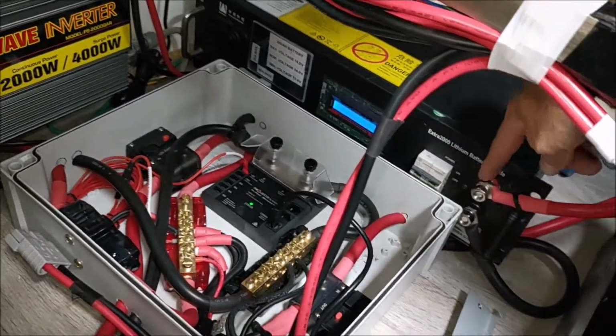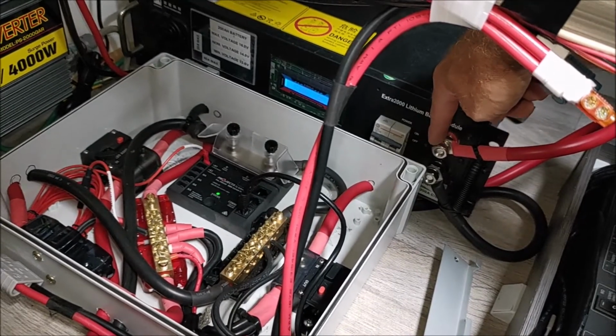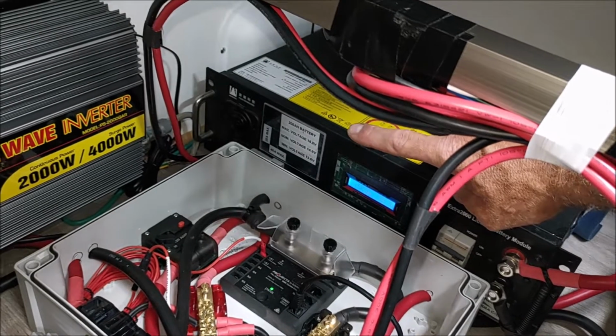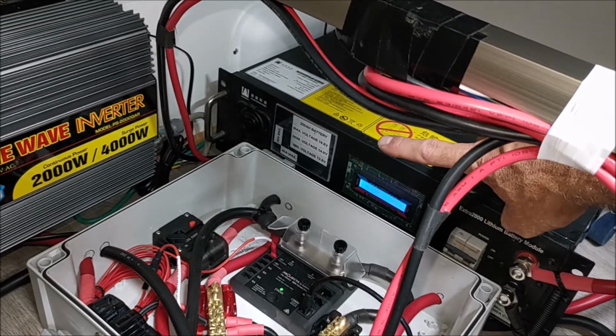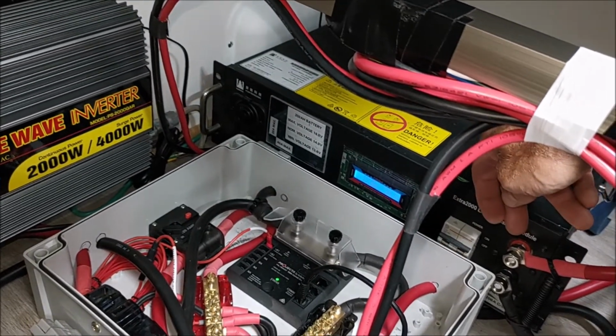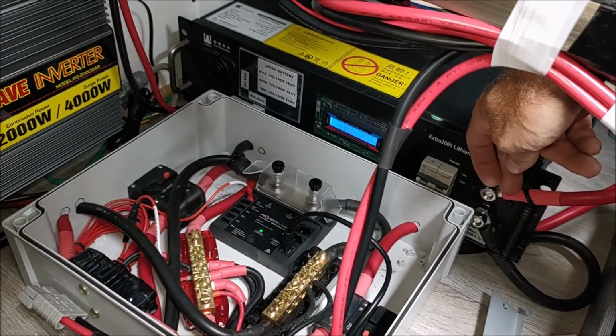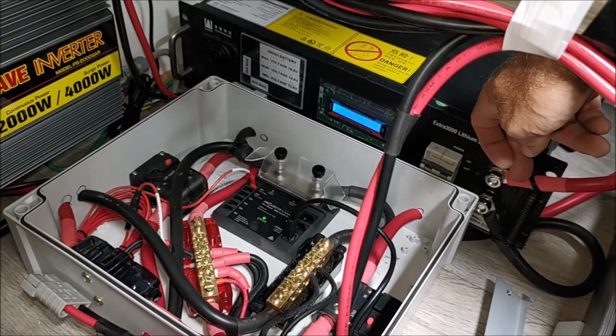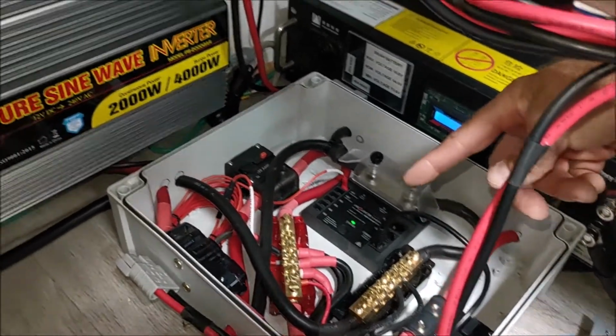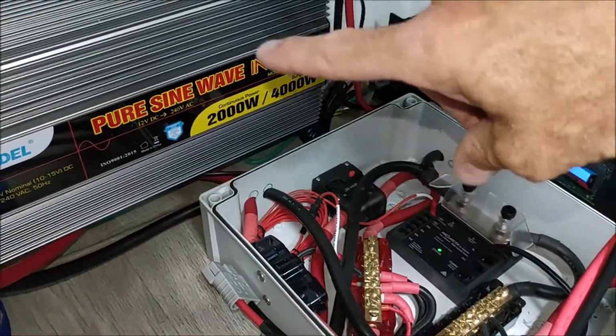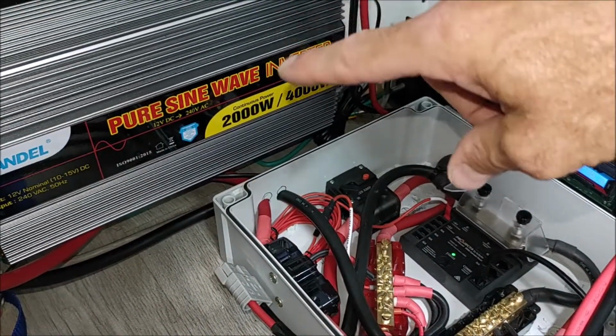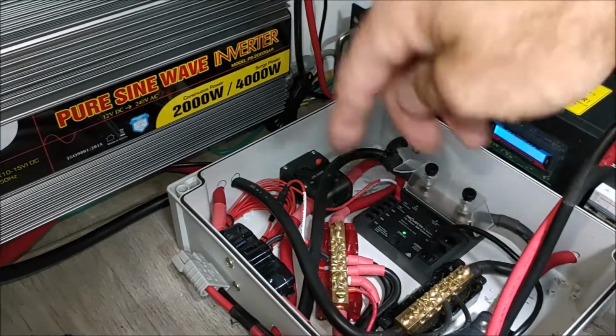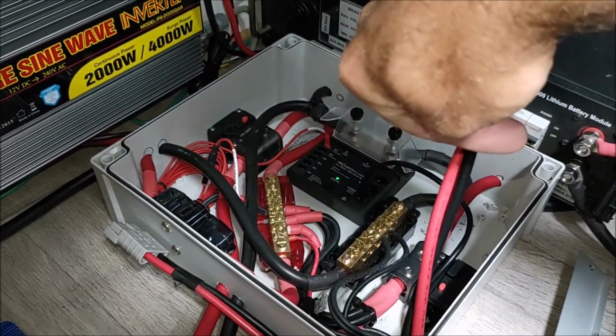The reason I've got these other connections is for the high current output, because there's a restriction through the BMS of a 40 amp output, so these connections don't run through the BMS. This is because the inverter, if there's a large load on it, will pull more than 40 amps, so I've run those connections separately.